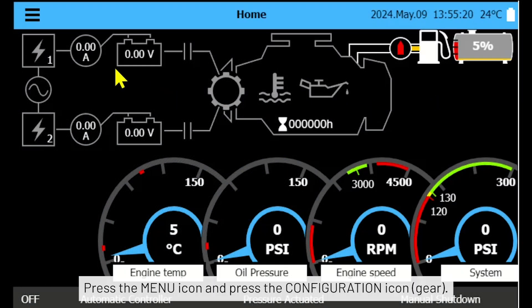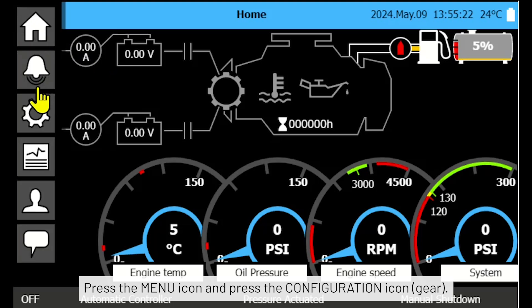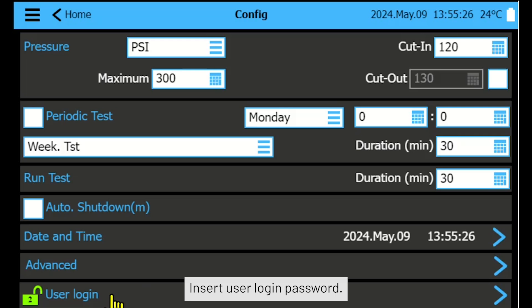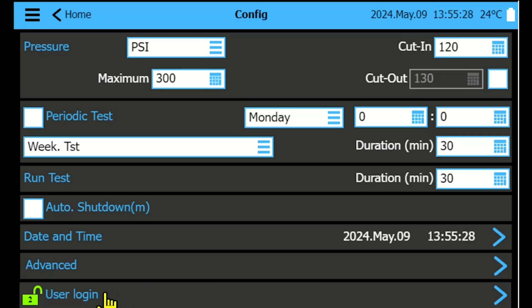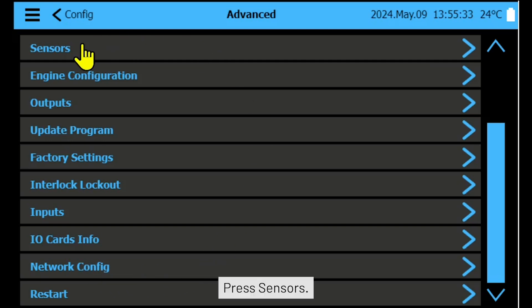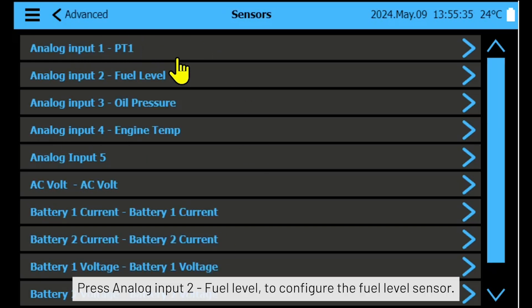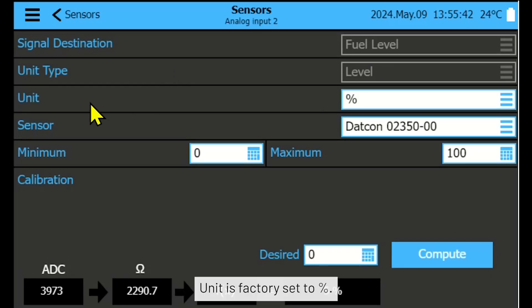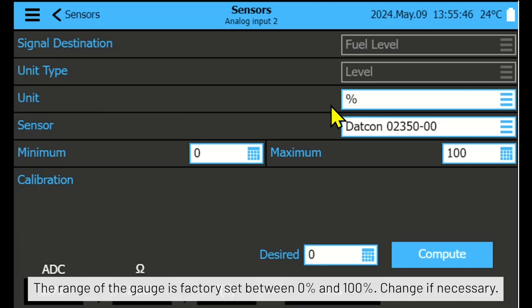Press the menu icon and press the configuration icon. Insert the user login password, press Advanced, press Sensors, press Analog Input 2 — Fuel Level to configure the fuel level sensor. The unit is factory set to percent and the range of the gauge is factory set.